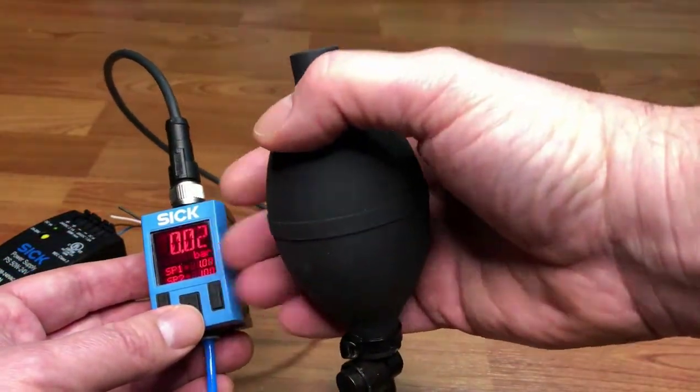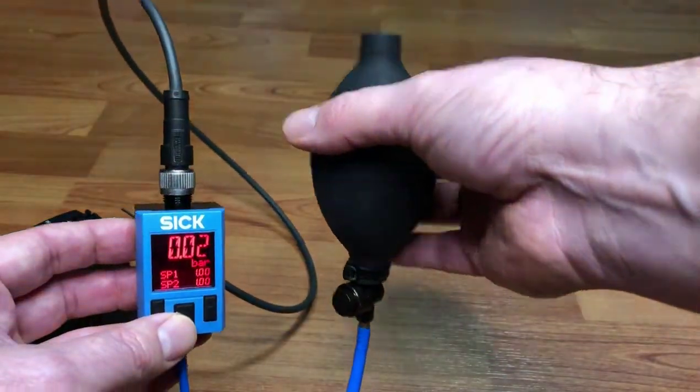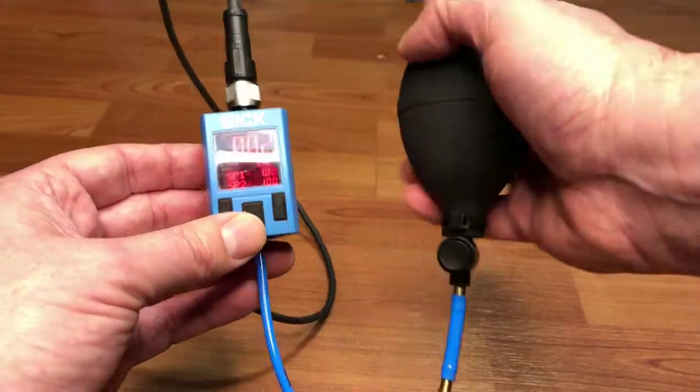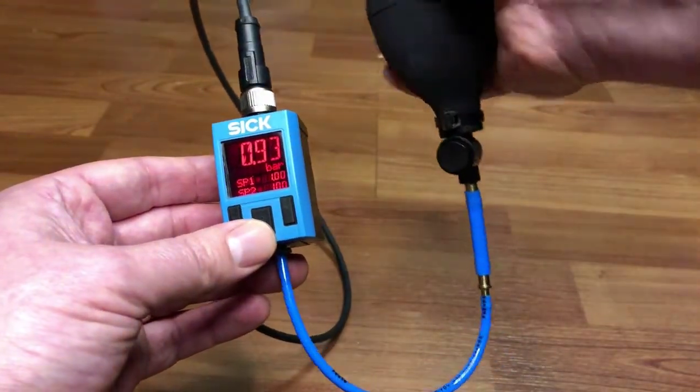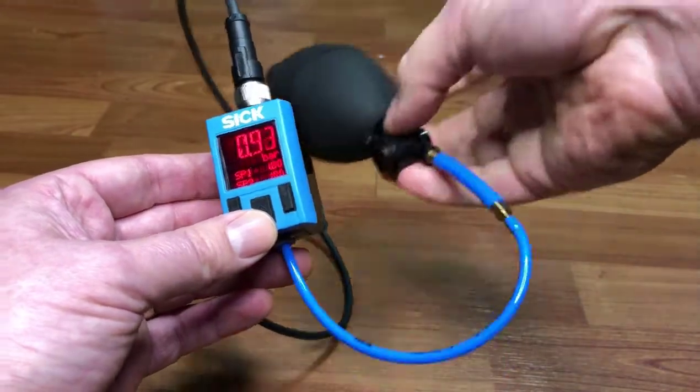What are the switch points? Let's check it out here and see what we can get to with the squeeze bulb. Right now it's set for one bar, so let's give it a good squeeze and see what kind of pressure ranges we can get to. I'm getting up to almost one bar, so we'd like to get a point where there's a switch point change.